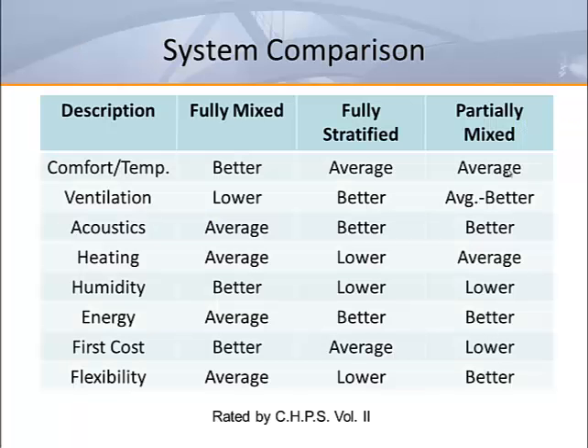This table compares the systems that we have discussed using several different factors of interest. For optimum temperature control in the space, a fully mixed system is superior. For IAQ and ventilation effectiveness, choosing displacement ventilation or underfloor may be a superior choice. For minimum sound levels, displacement ventilation and underfloor systems may be superior. For heating, displacement ventilation requires additional consideration. Fully mixed systems provide superior humidity control.